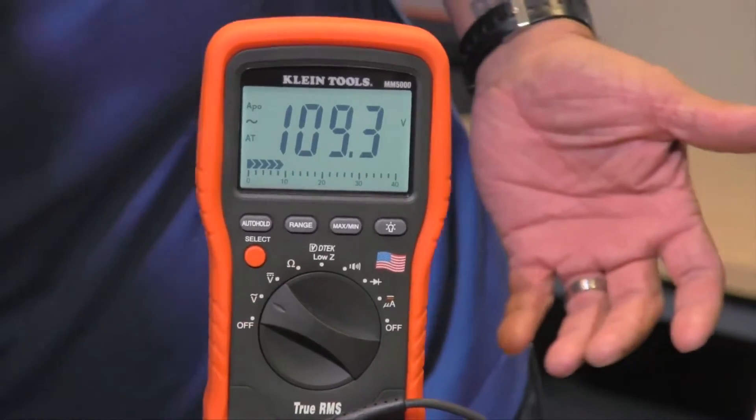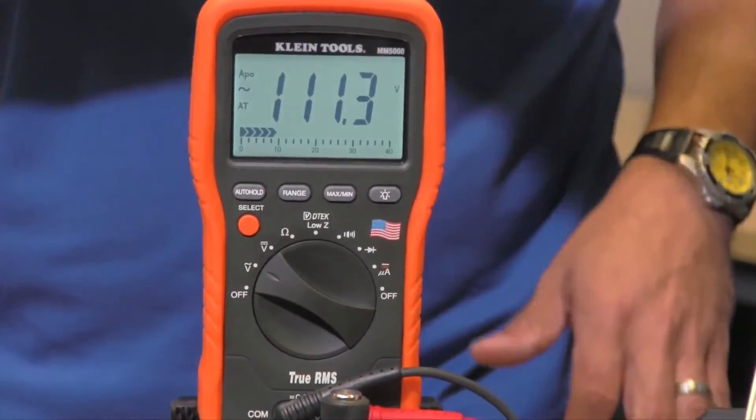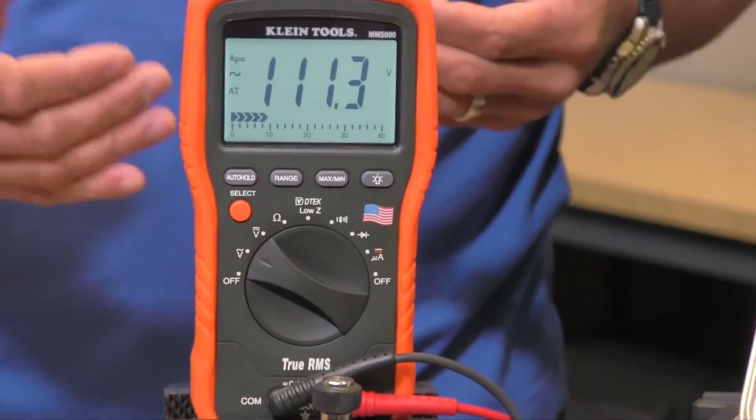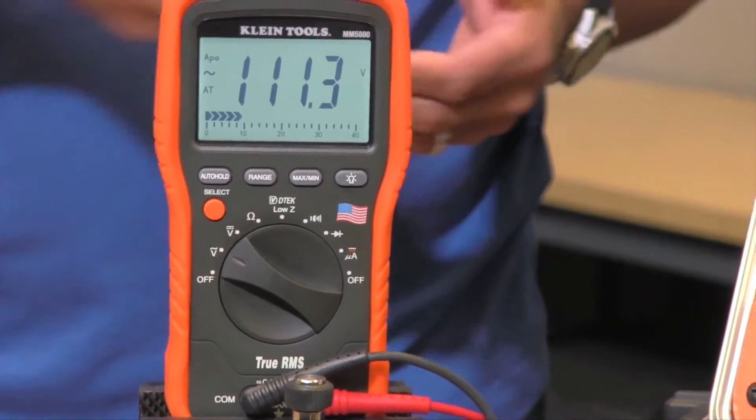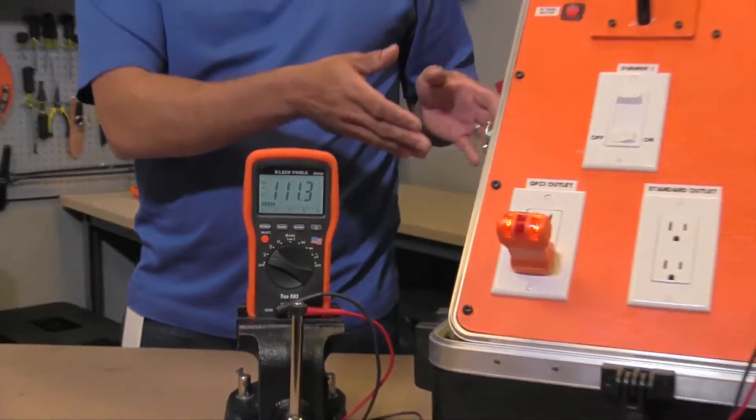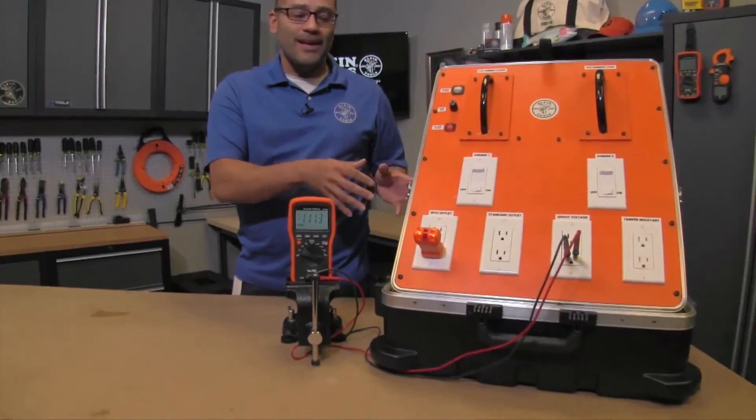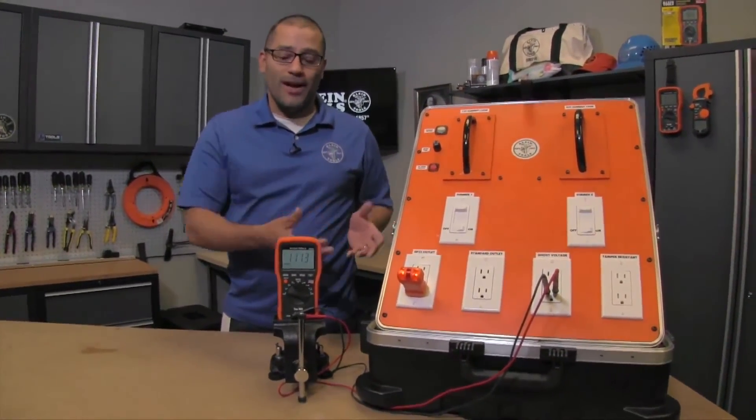You'll notice right now I'm reading approximately 109 volts out of that outlet. Now that's actually within specs and a regular lamp would probably run off of that. However since this outlet we know to be wired differently, if you were to plug in the lamp or the load it wouldn't turn on.